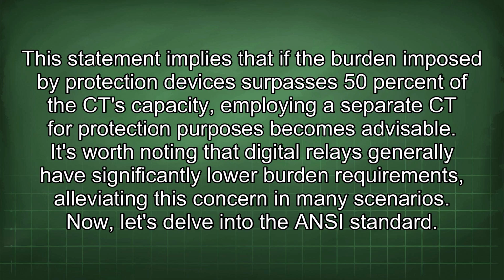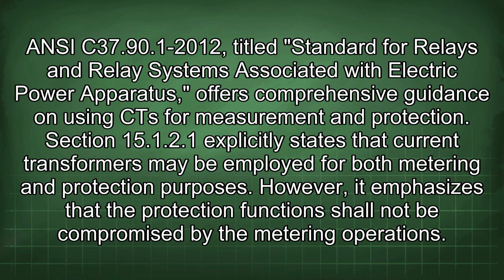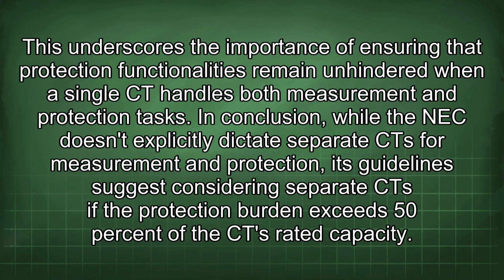Now let's delve into the ANSI standard. ANSI C37.90.1-2012, titled Standard for Relays and Relay Systems Associated with Electric Power Apparatus, offers comprehensive guidance on using CT for measurement and protection. Section 15.1.2.1 explicitly states that current transformers may be employed for both metering and protection purposes. However, it emphasizes that the protection function shall not be compromised by the metering operations.